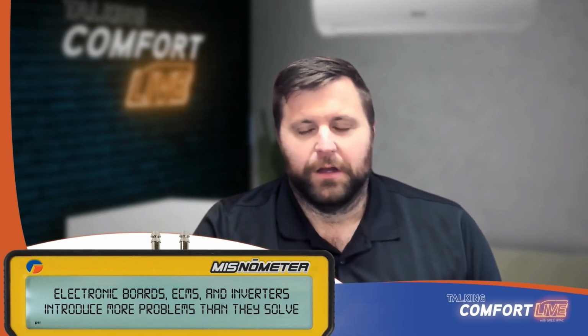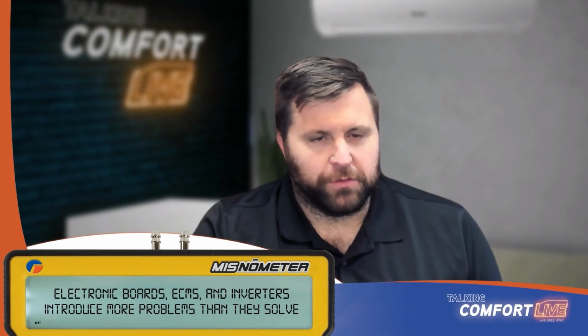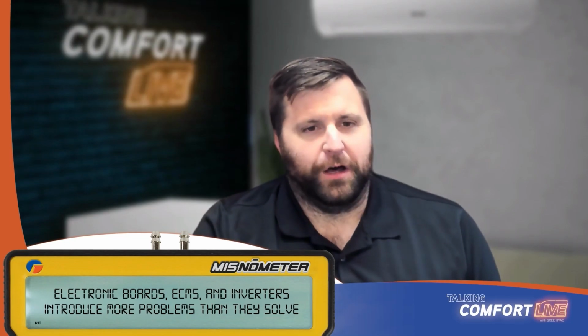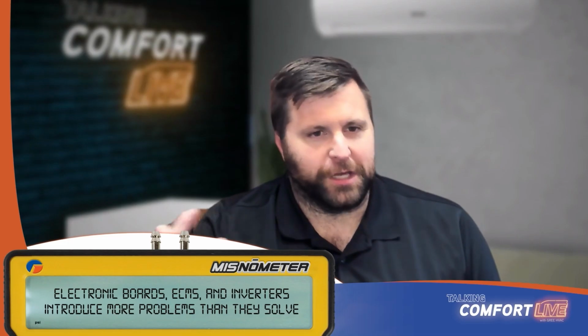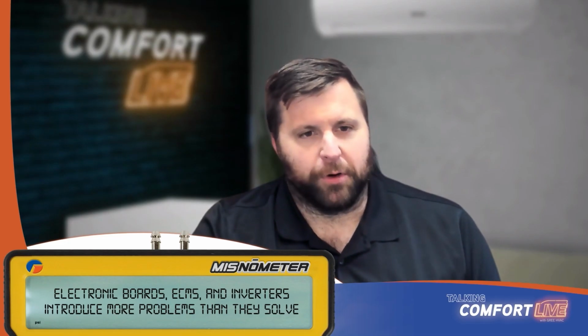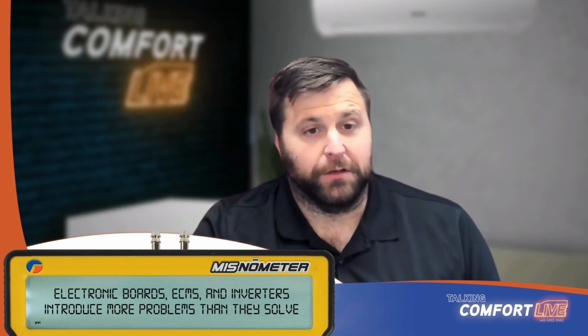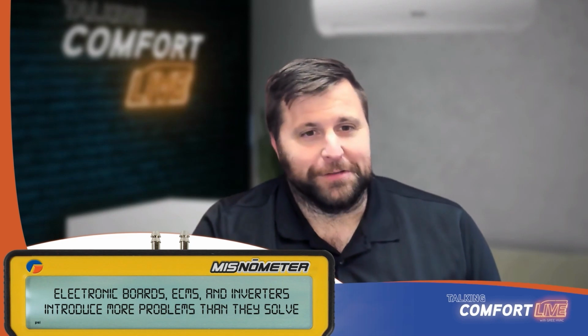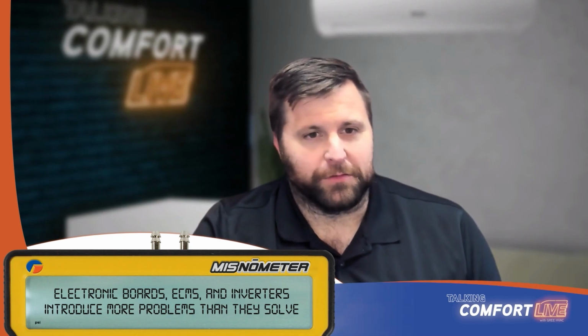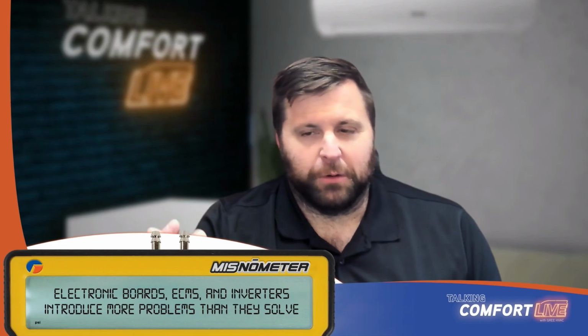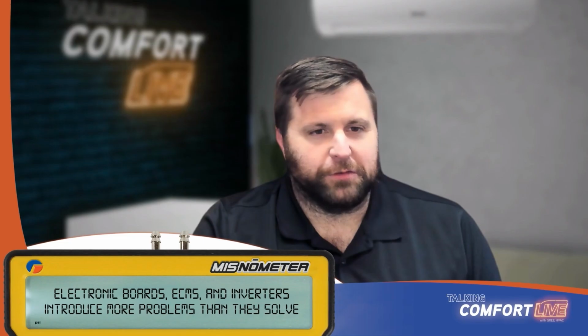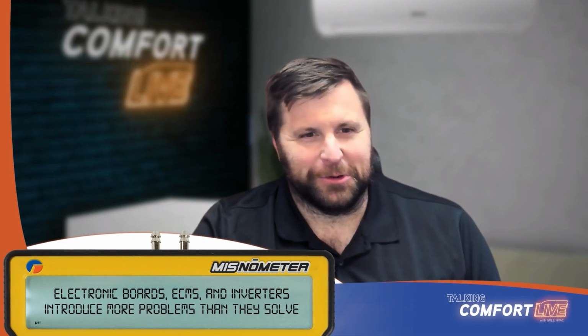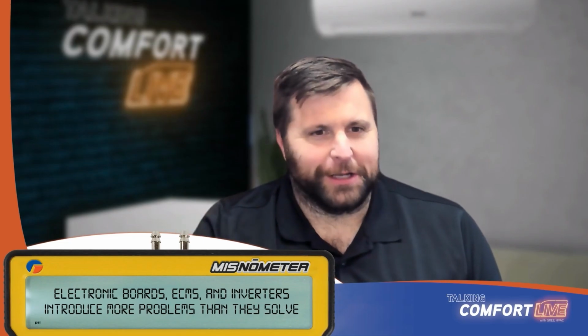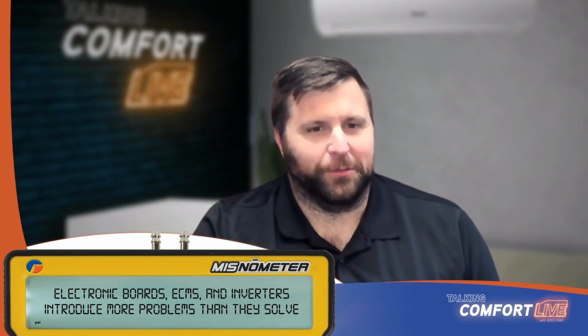So it just sits there, pressure gets hot, overload goes out, cools off, overload kicks back in. It just kept happening like that. And you end up with a permanently broken overload, stuck open inside that compressor, and now you're swapping out a compressor. Exactly. Which always killed me, because we would say we're saving so much money by not putting a low pressure switch on that unit. But what are you paying in terms of warranty on the compressor, that kind of thing?